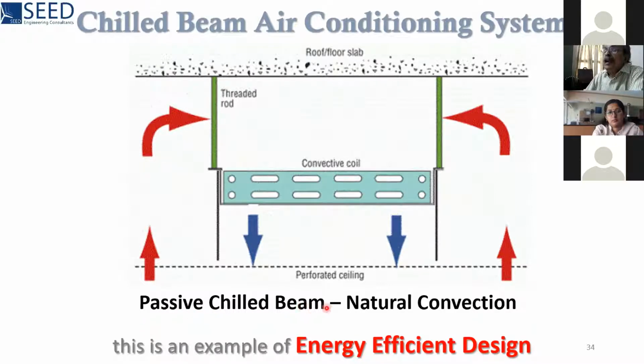The disadvantage of the passive chilled beam is that there is no provision for fresh air intake. So the only way is some fresh air may come in when you open the window or somebody opens the door. Since this is a natural convection process, it is known as a passive chilled beam. But this disadvantage of not having fresh air is compensated in an improved version.